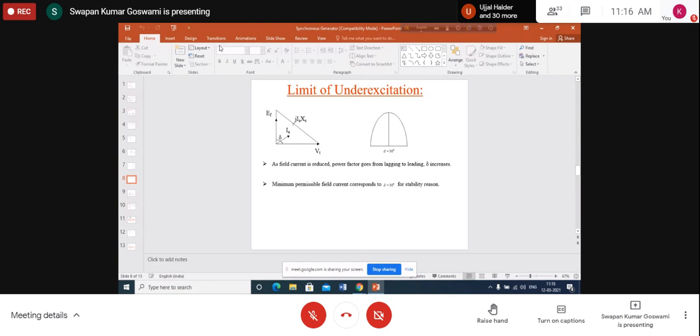তার ফলে reactive power supply টা বেশি হয়ে যাবে. Reactive power supply বেশি হলে we need some inductive load to be connected to the system. Who can be that inductive load? Generators now can become that inductive load. It will be supplying active power, no question about that, because it has to supply the active power. But this reactive power, it has to consume.